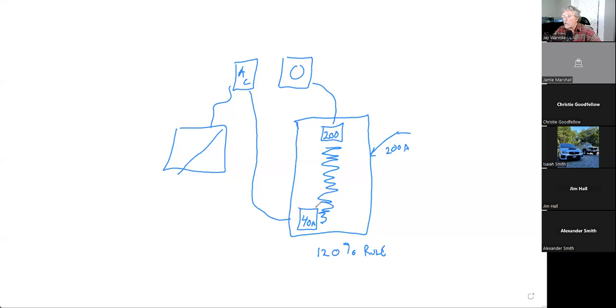The reason for that is you don't want to be doubling up power. All of this power is going to be leaving to go to loads at different breakers. And if I'm feeding in from this side and I'm feeding in from this side, I'm not going to be doubling up. At no point is this bus bar going to be exposed to more than the 200 amps. If I had this up next to here and all the loads were down below, I might overfeed that bus bar. So that's the 120% rule. So I can go to 40 amps under this scenario.